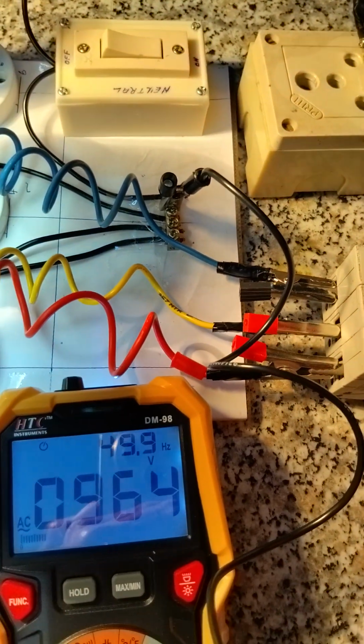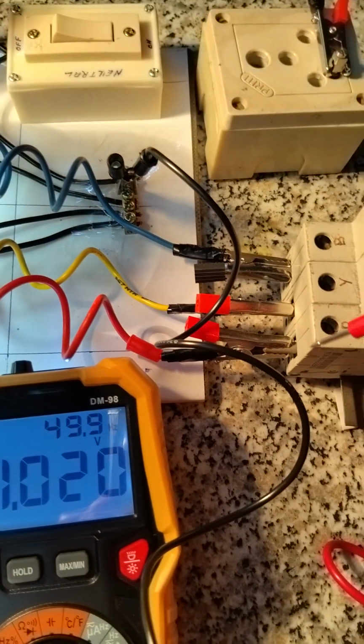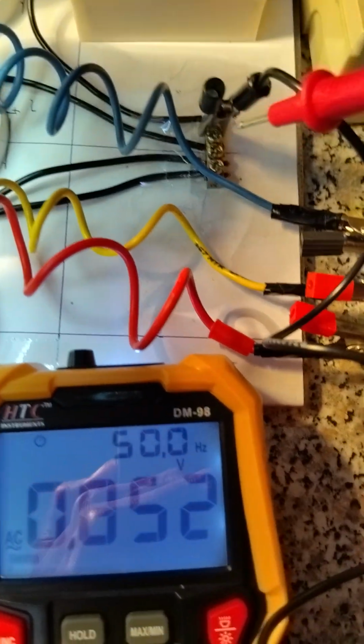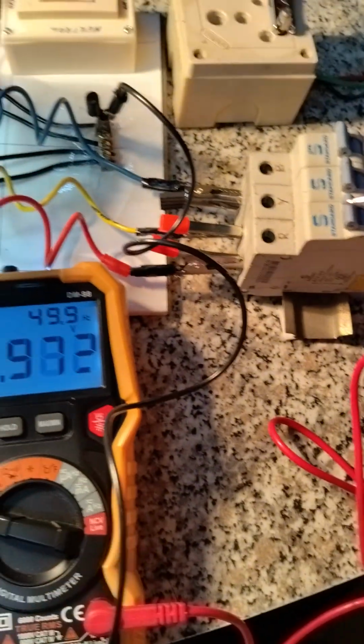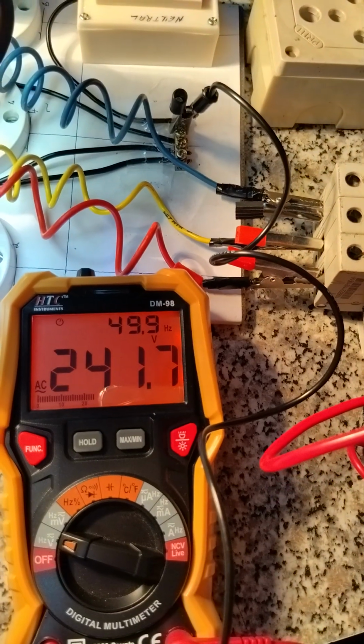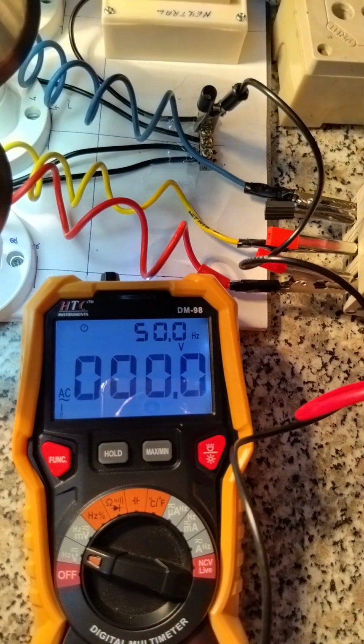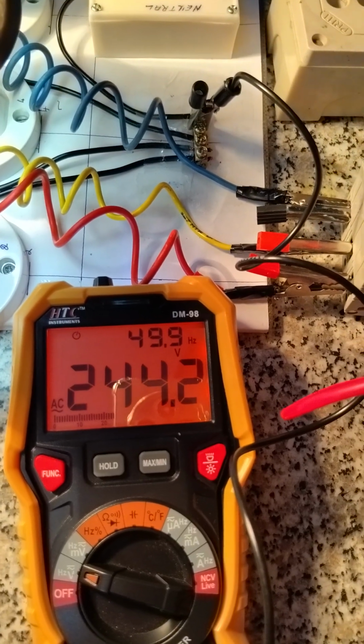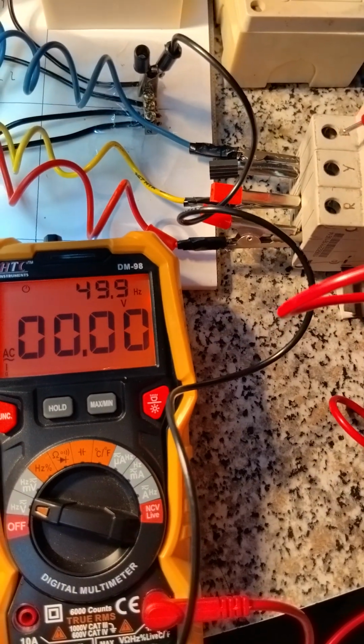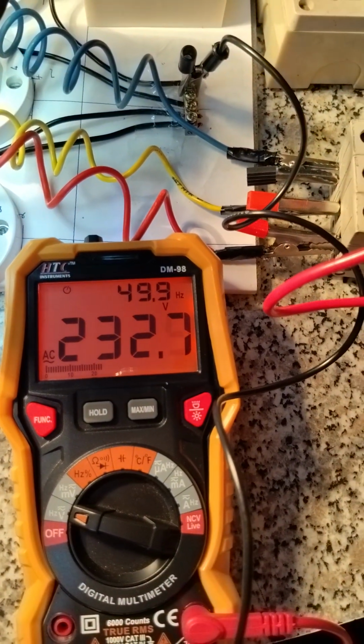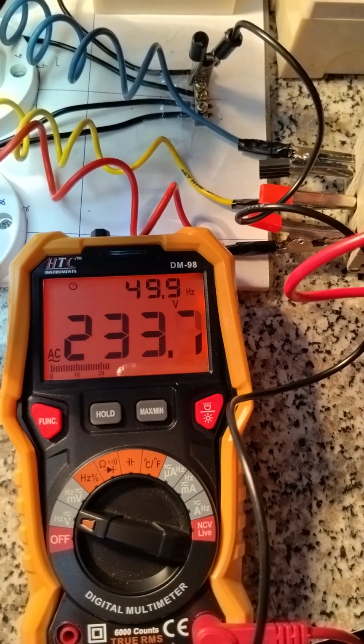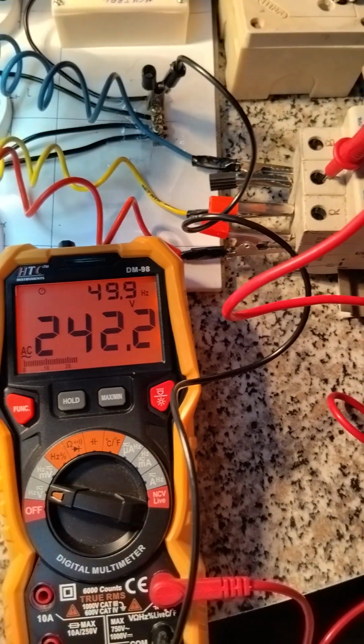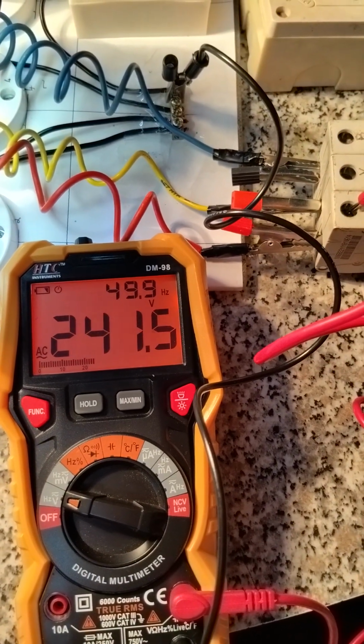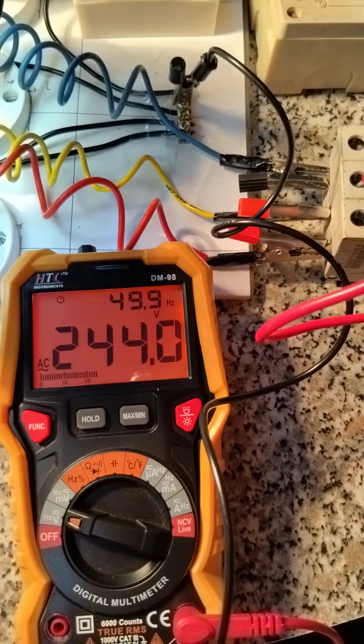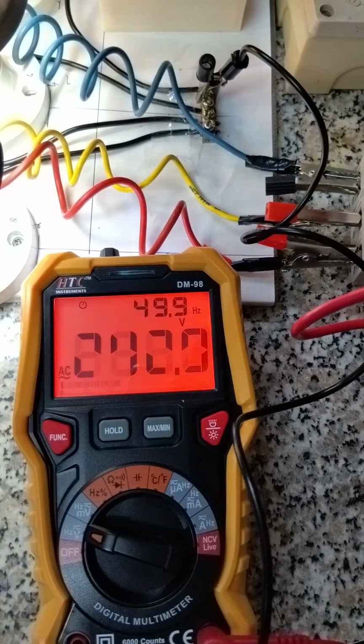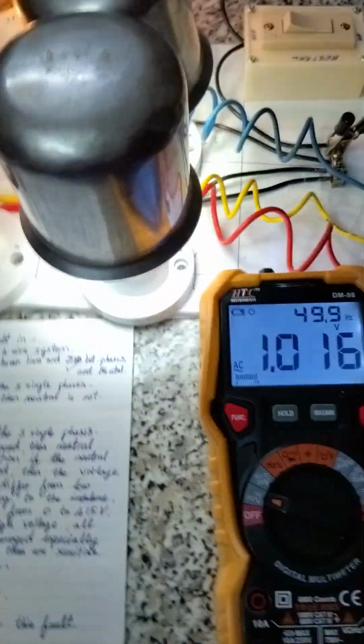For that we will check the individual voltages between each phase and neutral. Please note the readings. First between R and neutral, it is 240. Between Y and neutral, 244. Between blue and B and neutral, 232. More or less, these are all same within the limits. So these slight variations we can ignore.